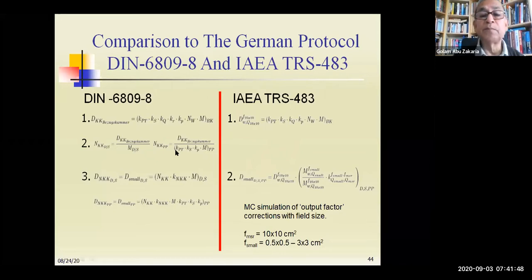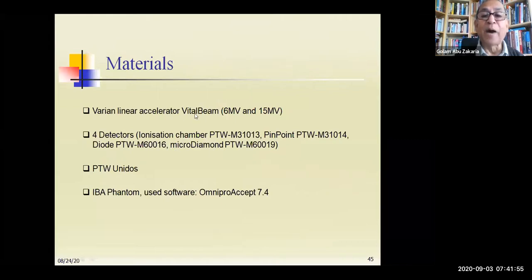When you have some protocol, you can understand very well how it's functioning. From the materials, we use our VitalBeam linear accelerator for 2 energies, 6 and 15. And we have taken 4 detectors: the normal detector, then a pinpoint, a diode, and a microDiamond. And of course the Unidos, and the phantom, with the software OmniPro. All medical physicists know these measurement instruments in their hospitals.